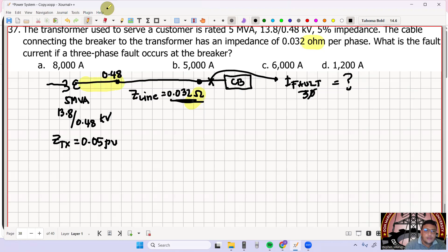So Z line in per unit is equal to Z actual over Z base, which is 0.032 over Z base. Z base is V squared over S, so that is (0.48 kilo) squared over 5 MVA. So it is 0.032 over (0.48 times 10 raised to 3) squared over 5 mega, which is equal to 0.694 per unit.